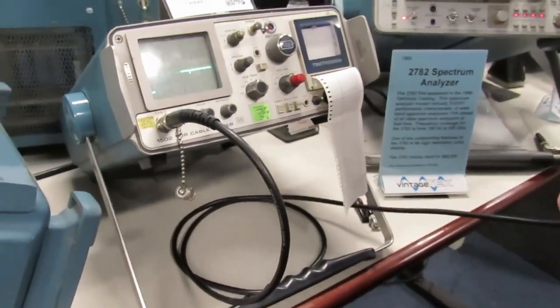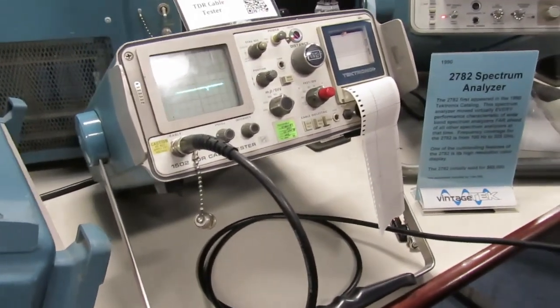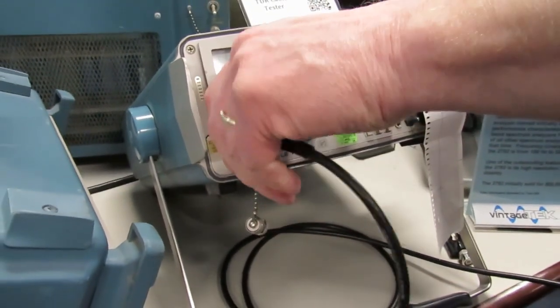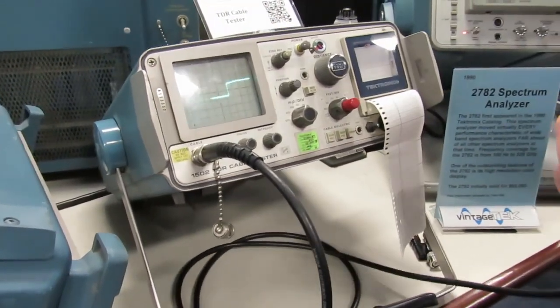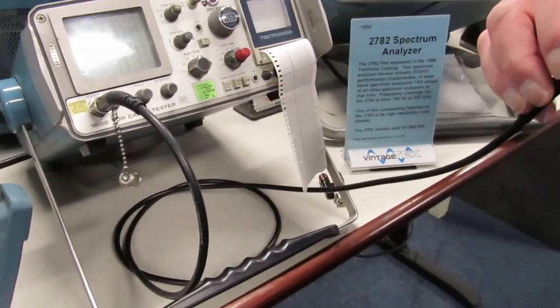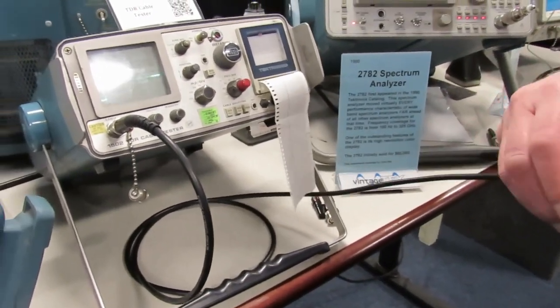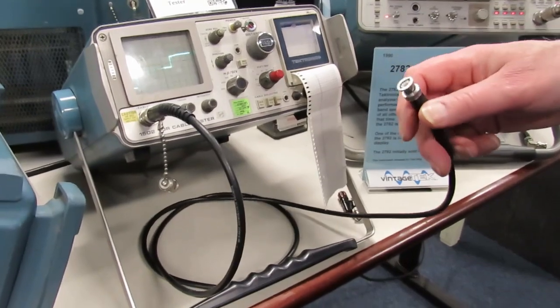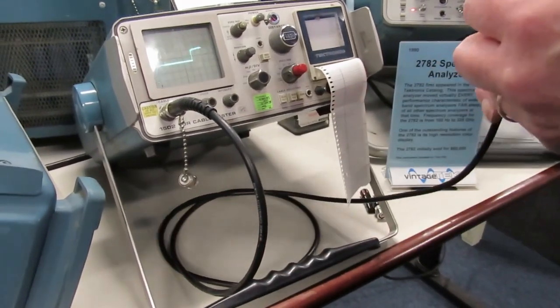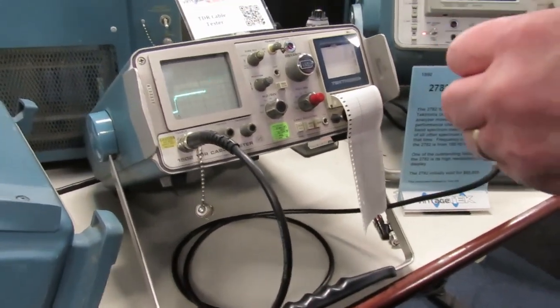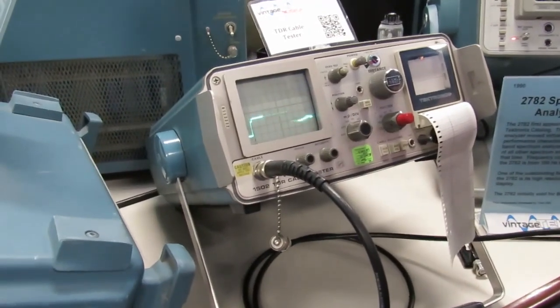So a time domain reflectometer then, right? Yeah. It's sending a real narrow pulse like that, and when it reaches the end of the cable, if it's terminated right, no problem, but if it's not, it reflects back. So you can tell that's an open termination.